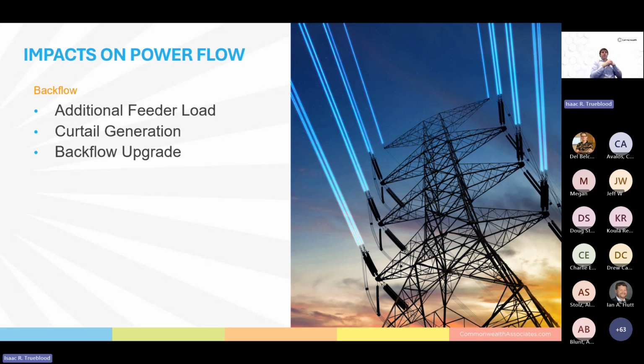Another mitigation option is to allow the distributed energy resources to curtail their generation under low load conditions. By installing instrument transformers on feeders that communicate with a distributed energy resource, it can sense the load and curtail its generation in real time to not exceed the load, preventing backflow conditions. This is often a large undertaking and is often non-financially viable, especially for independent distributed energy resource owners. But for a small utility looking to have some of its own generation, it can be a solution without the need for renegotiating those contracts or upgrading the system's feeders.